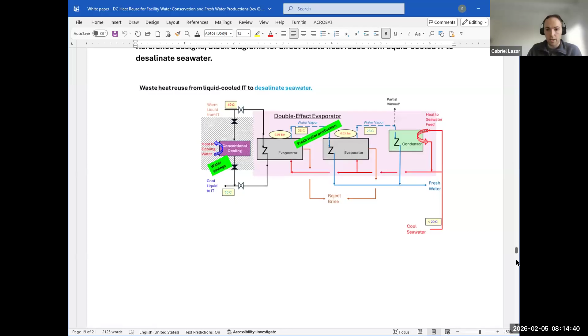If you go down a few tens of meters from your intake pipe, your water is already fairly cold. There's a thermocline pretty much almost everywhere. Here you can see, from 40 degrees C, first stage evaporating at 35, second stage evaporating at 25, and final cooling at 20. I picked a 5 degree approach as being reasonable. Obviously, the bigger the delta T you have available, the smaller equipment you need for the evaporator.